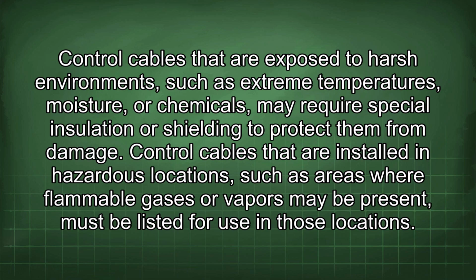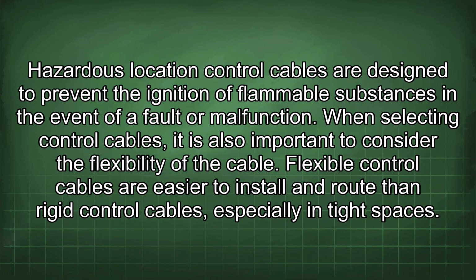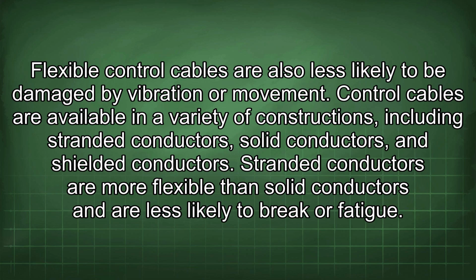Control cables that are installed in hazardous locations, such as areas where flammable gases or vapors may be present, must be listed for use in those locations. Hazardous location control cables are designed to prevent the ignition of flammable substances in the event of a fault or malfunction. When selecting control cables, it is also important to consider the flexibility of the cable. Flexible control cables are easier to install and route than rigid control cables, especially in tight spaces. Flexible control cables are also less likely to be damaged by vibration or movement.